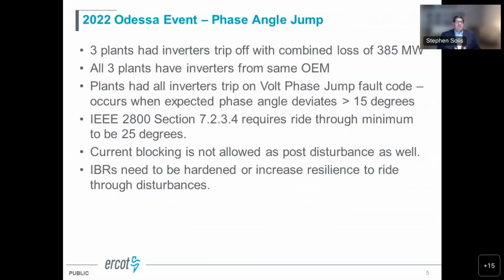And just to give a couple of examples with the recent Odessa events, phase angle jump is one example. In our first Odessa event, we had phase lock loop, PLL, loss of sync. We went through, identified that as an area of improvement. Several units disabled that particular feature. But then the next thing got them, which was phase angle jump in some instances.